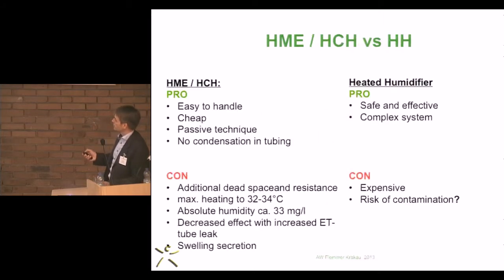Now, heated humidifiers as compared to the passive humidification devices that are very easy to handle. They are quite cheap. It's a passive technique, but rather no condensation is actually occurring in the tubing. However, as I've shown, the absolute humidity we can achieve with these devices is not more than 32 to 33 milligrams per liter. The heated humidifiers are safe and effective, but they are quite complex systems, although the modern systems are rather internally regulated. They are expensive, and the question is whether or not there is a risk of contamination. What would you say? Is there a risk of contamination or not?